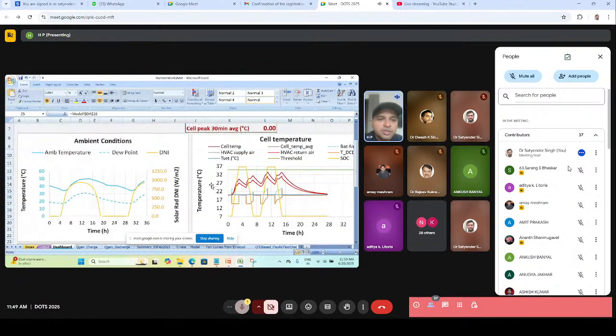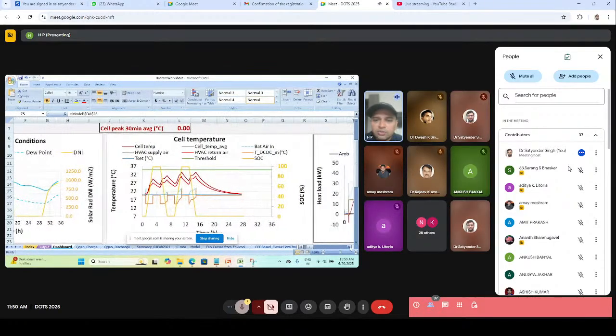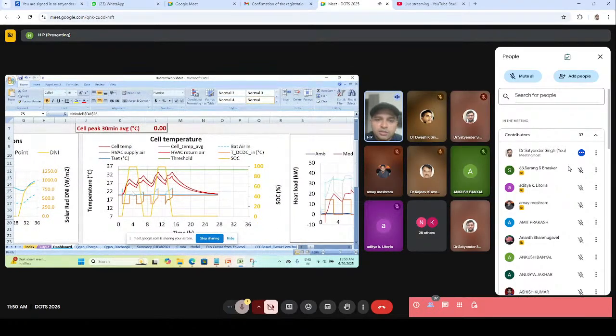So for this given ambient profile, which starts from around 40, goes to somewhere around 35, and sometimes 50 degrees C also, and then goes down, that's the temperature for that kind of ambient condition. If I have to deliver 2 cycles, or here it shows 4 cycles, the battery temperature starts rising when we are charging. This yellow line here shows when it goes up, it's charging; when it goes down, it's discharging; and when it is flat, it's basically a rest period. So it's a typical profile of any battery energy storage system.